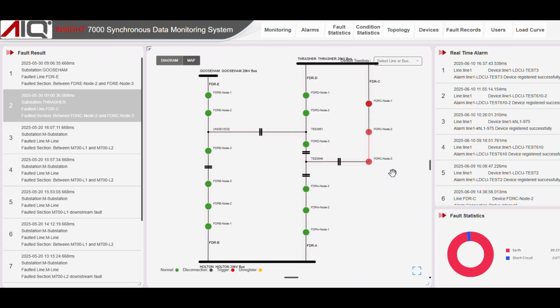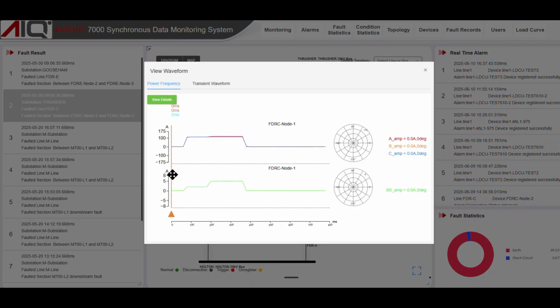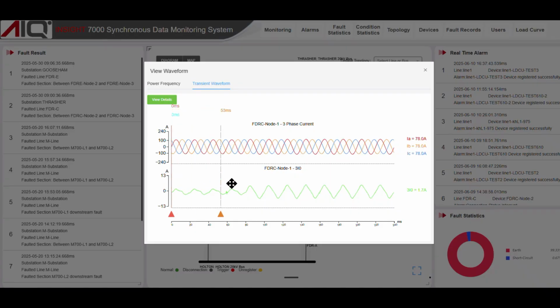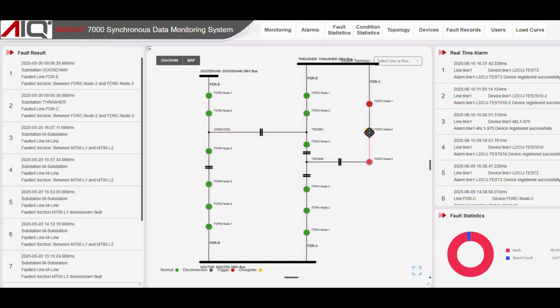If we drill more deeply by looking at the waveforms from each node, starting with the first node, we first look at the 3-phase and 0 sequence current, magnitude and phase, and then at the transient waveforms. By moving the cursor to the fault positions, we can see that the zero sequence fault current is very small at 5 amps, and its angle of 1 degree is in phase with the A phase current. The transient waveform also shows the small fault current magnitude and the angle relationship. If we look at node 2, we see the similar magnitude and phase and the transient waveform as the first node.